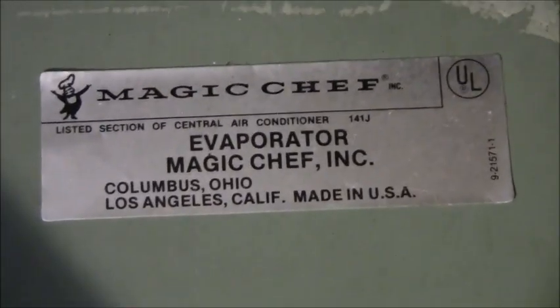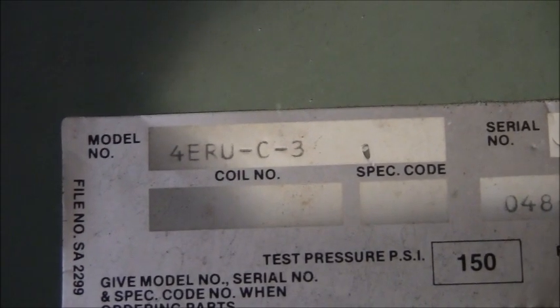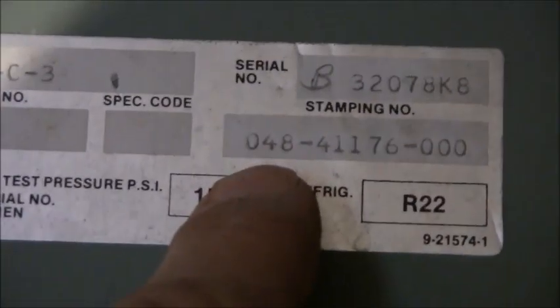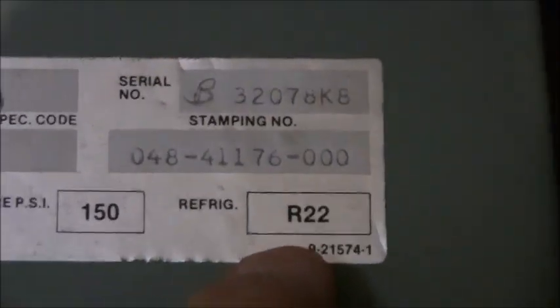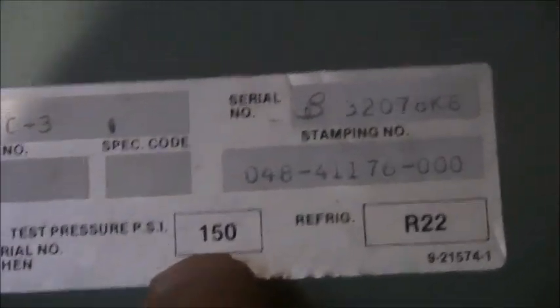Now here's the model of the evaporator. So you can see it's a Magic Chef, and this is the model number. And because of that model number, the unit, actually hold on a second, we have another number over here, 048. This pretty much is telling me it's a 4-ton unit. Okay, I believe, and it's R22. What this does not tell you is whether this is a TXV or a piston or a fixed metering device. I'm going to make an assumption because I can't gain access to this. This system is so old that you cannot gain access to the inside of this system.